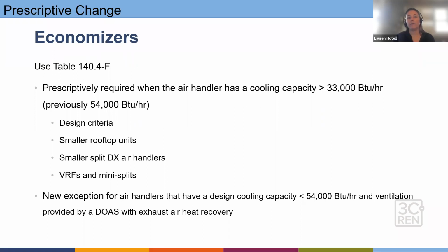Under this code cycle, economizer requirements are being broadened to lower capacity units. So these are prescriptively required when the air handler has a cooling capacity of more than 33,000 BTU per hour. This was previously 54,000. So we are now focusing on smaller rooftop units, smaller split DX air handlers, and VRFs and mini splits.